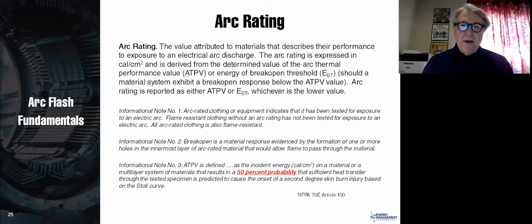The caveat there is if you have a shirt that's rated for, let's say, 10, and your PPE is rated for 12, you say, well, I can add those up and now I can work on something that's 22 calories. No, you can't. You cannot work on something that's that many calories unless those two pieces have been tested in combination with one another. So if you have a shirt that's rated 10 and you put coveralls over it that's rated 12, you're still 12. You are whatever the highest of those two pieces of equipment. You can't layer and add the two pieces together under the standard. However, layering does provide a lot of protection. So it's a good thing morally to know that in reality, you are reducing your chance of a burn significantly. So I hope that was clear there.